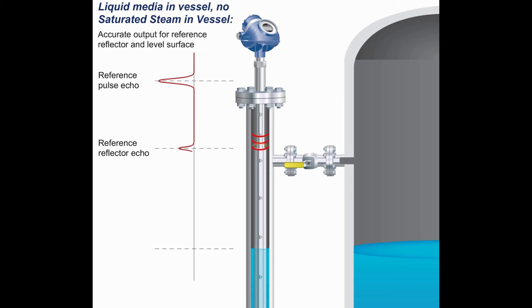The second echo comes from the dynamic vapor compensation reflector at the point where the dimension changes. The lower echo at the surface level occurs due to the pulses hitting the water surface.